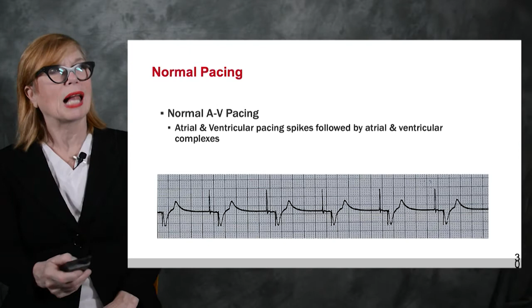Okay, so this tells us that we have a DDD. And this, if we knew that's what it was set to, it doesn't matter. We are spiking our ventricle, and the ventricle is paced at the atrial rate. So DDD means how many chambers are paced? Right, dual. How many chambers are sensed? Right, dual. And what's the response? Are you inhibited and triggered? Yes, if it's D, you're inhibited and triggered. Dual, DDD. Dual chambers paced, dual chambers sensed, and the dual response triggered and inhibited.